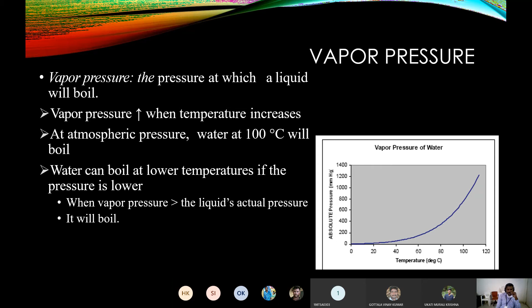Cavitation is the phenomenon of formation of vapor bubbles in a flowing liquid in a region where the pressure of the liquid falls below the vapor pressure, and the sudden collapsing of these vapor bubbles in a region of higher pressure. Because of this collapse, a severe pressure rise takes place and hits the surfaces. The pressure wave removes material from the surface and small cavities are formed. That is why we call it cavitation.